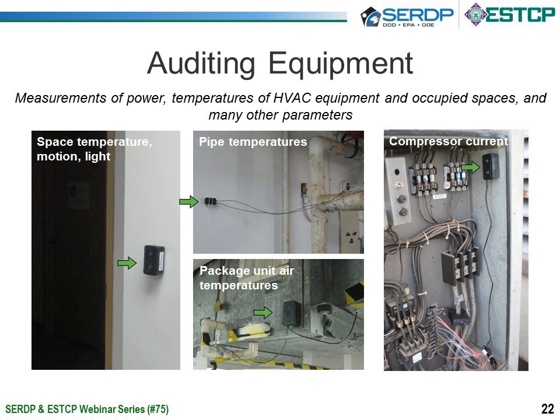And then one of the key areas is looking on the right here at current or power measurements. So most buildings have an entire building utility meter set up to get usage for the entire building. But to really understand what's going on, we need to do what's called sub-metering. So installing these low-cost power measurements at key users such as chillers, compressors, and other equipment to really understand what each of the pieces of equipment are using in the system.